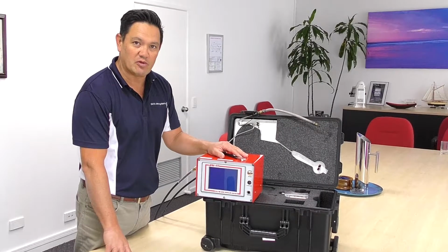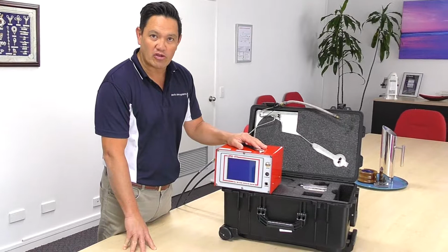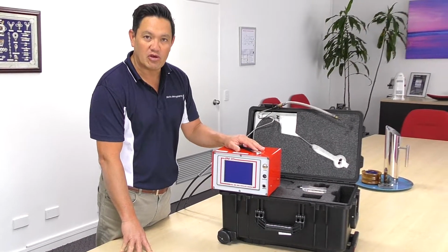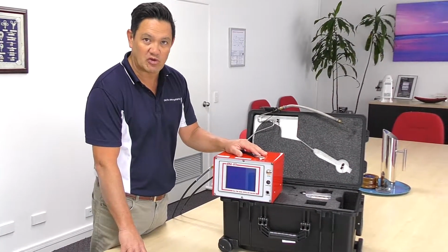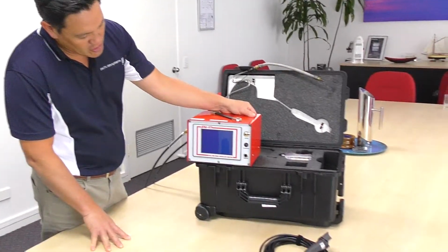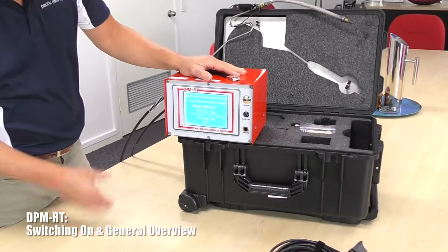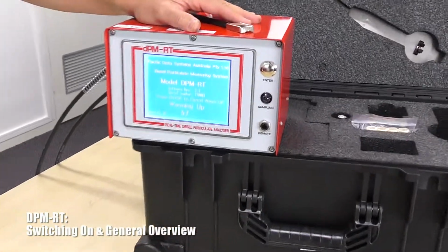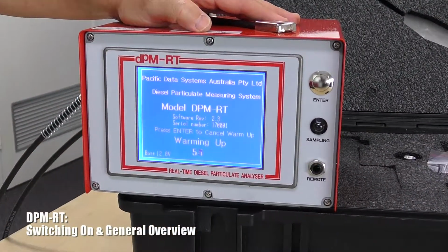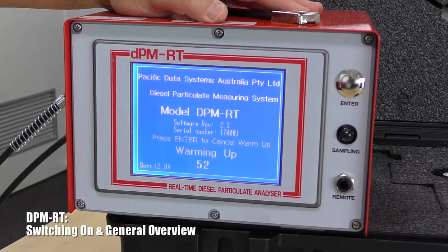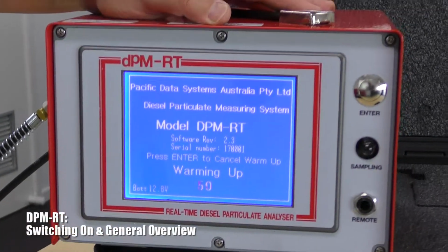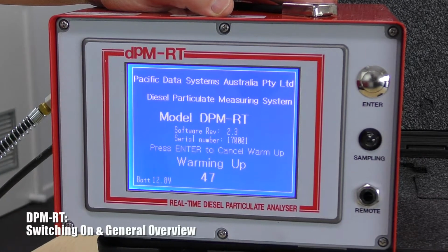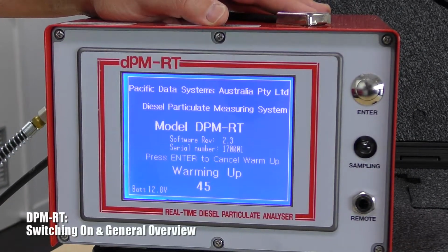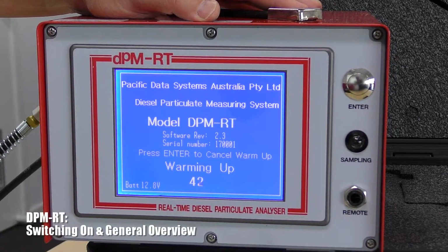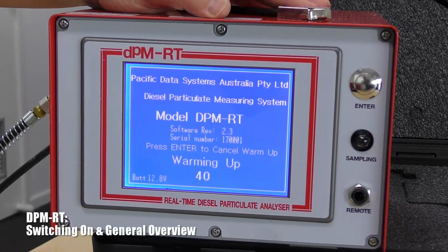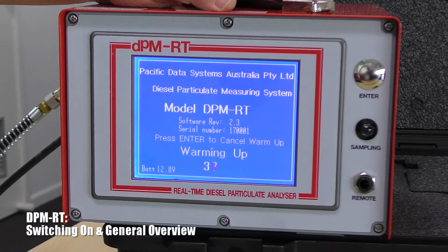In this next segment, we're going to talk about switching the unit on and a general overview of the display after it's switched on. Switch the unit on. The front display will indicate our company name, the name of the instrument, the model of the instrument, the software version. In this instance, it's software revision 2.3, the serial number, which should correspond to the label on the back of the instrument, and it will indicate that it's warming up.